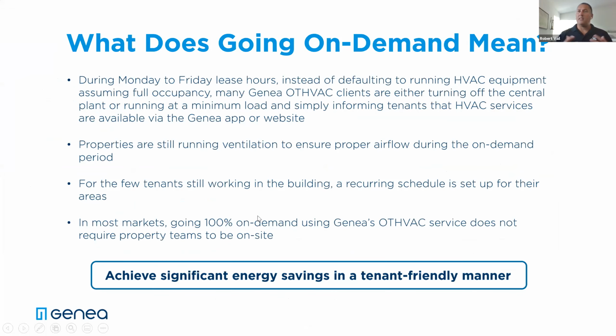Let's bring in the concept of going on demand. What does on demand really mean? During Monday through Friday normal lease hours, instead of running the building on a normal schedule, you reduce the equipment runtime and go on demand, meaning you turn off the central plant, run to minimum loads, and simply inform tenants that HVAC services are available via our app or website.